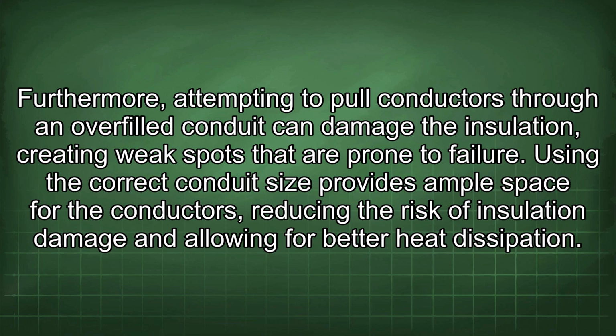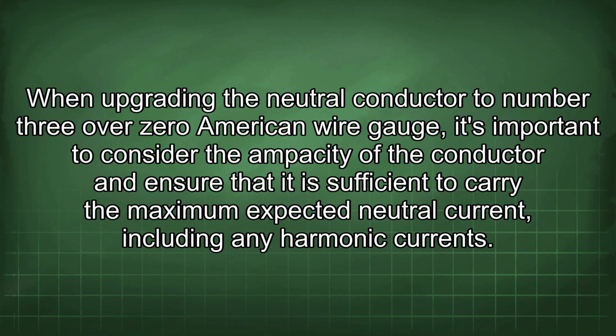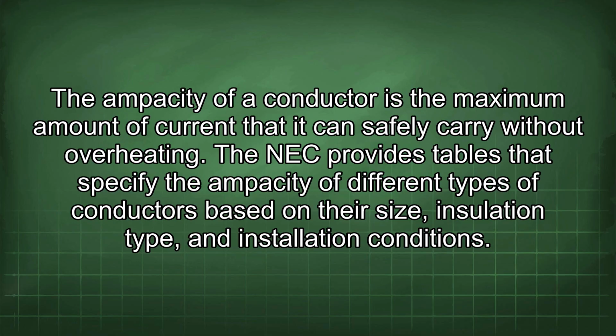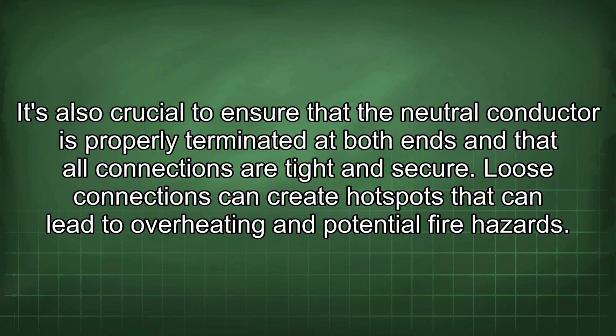When upgrading the neutral conductor to number 3/0 American wire gauge, it's important to consider the ampacity of the conductor and ensure that it is sufficient to carry the maximum expected neutral current, including any harmonic currents. The ampacity of a conductor is the maximum amount of current that it can safely carry without overheating. The NEC provides tables that specify the ampacity of different types of conductors based on their size, insulation type, and installation conditions. It's also crucial to ensure that the neutral conductor is properly terminated at both ends and that all connections are tight and secure. Loose connections can create hotspots that can lead to overheating and potential fire hazards.